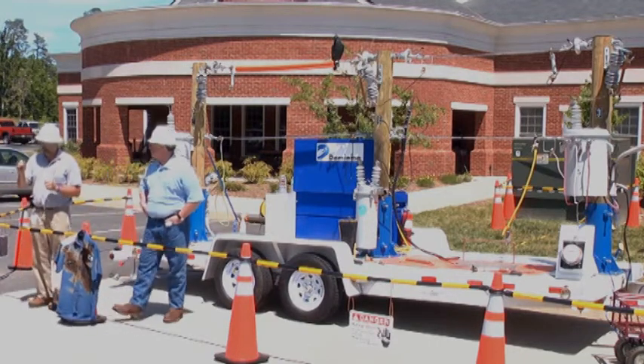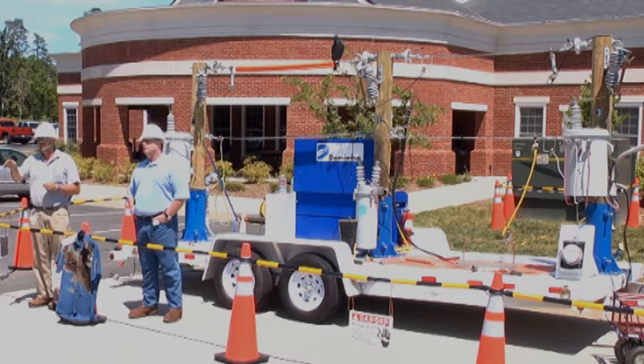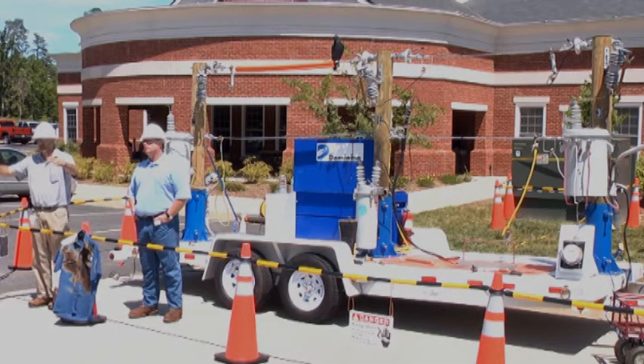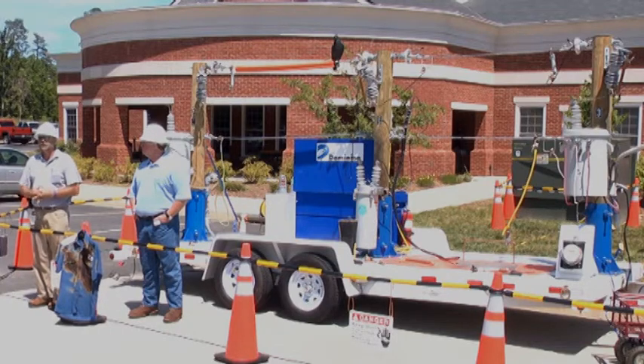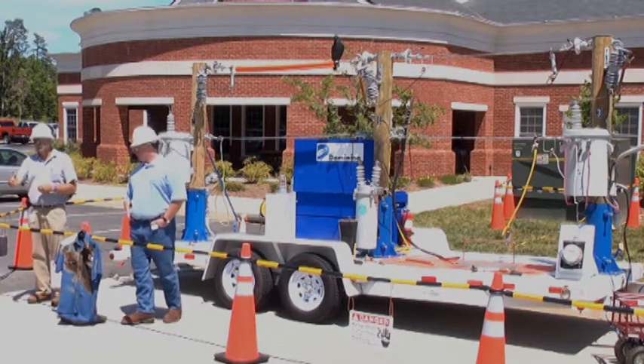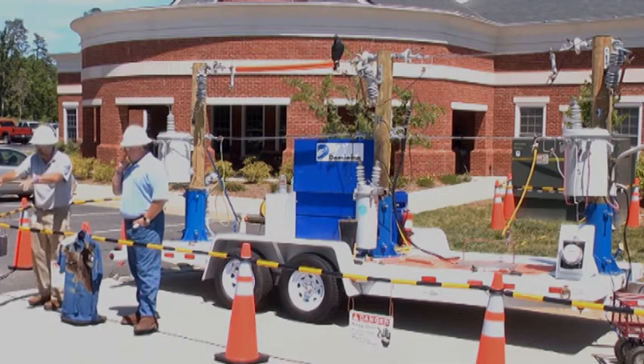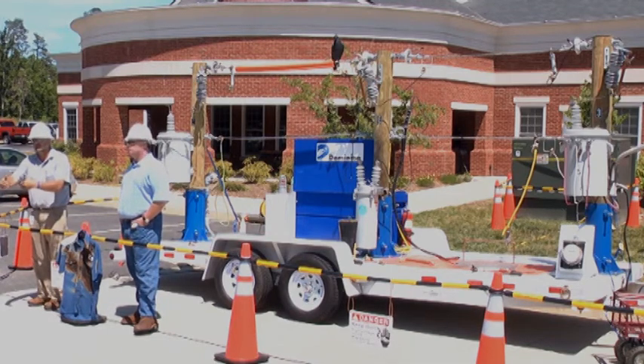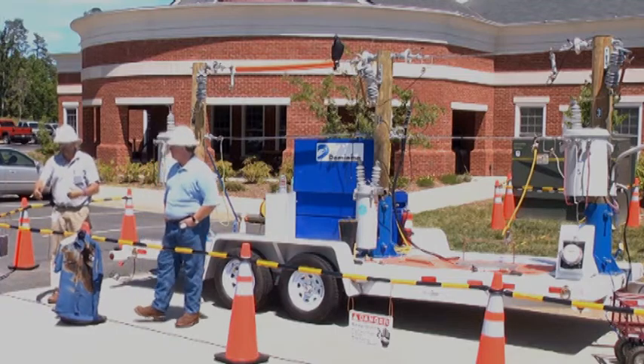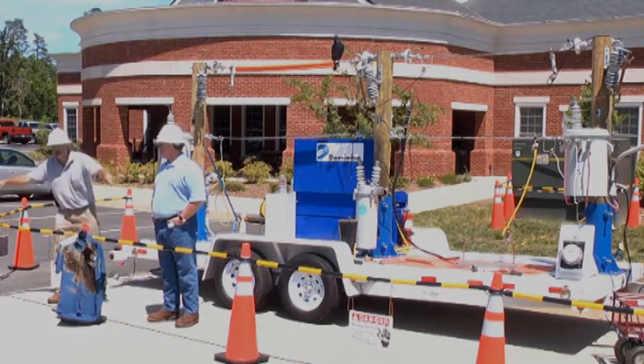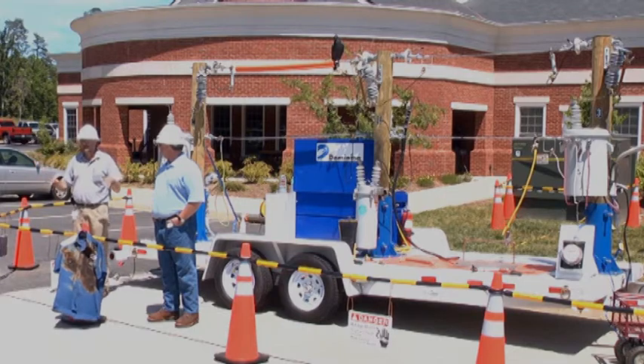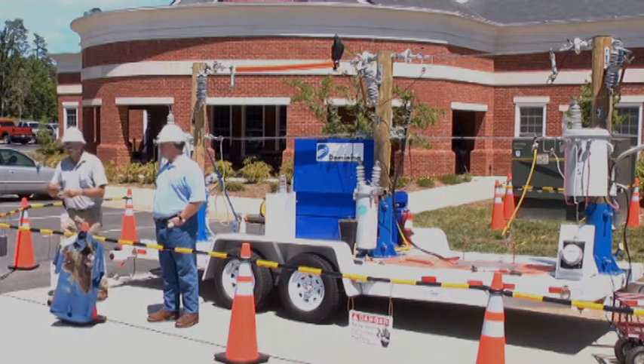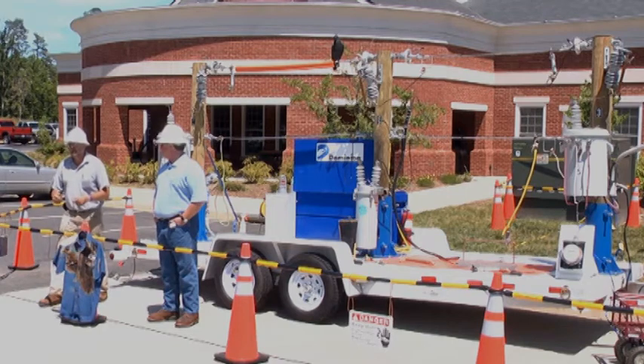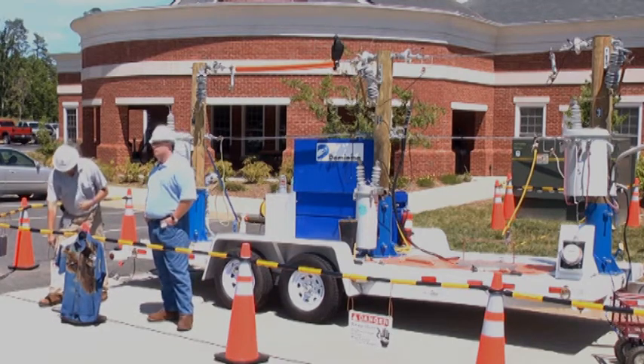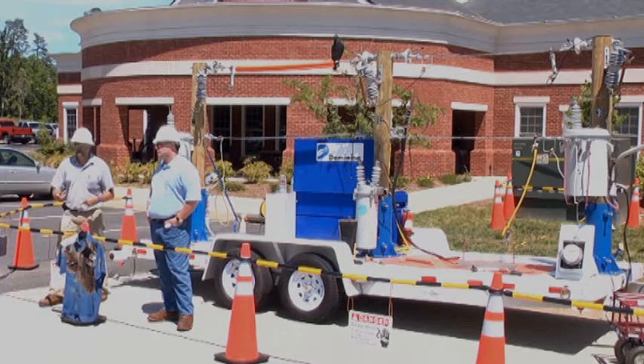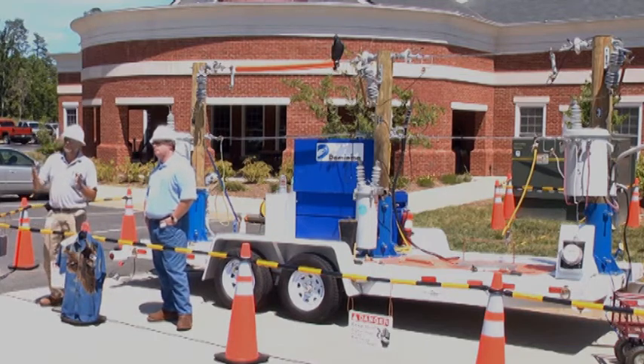Have you ever taken a pebble and thrown it in a pond, and seen what happens to the water? There's a thing called step potential. Wherever our wires are on the ground, if you go out a couple of feet, that's the highest potential. Then it steps down a little bit out to earth, and steps down again in gradient rings. If you're walking with your feet far apart, and you're in two different gradients, the power can come in one foot and go out the other and kill you. That's the difference in potential, so we recommend 30 feet.